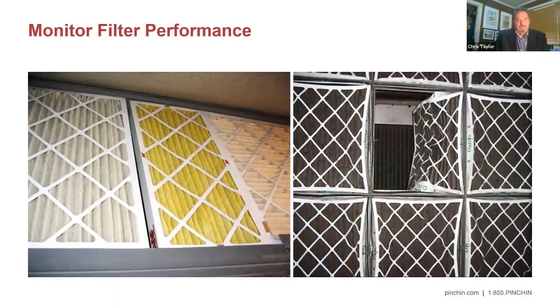Here's where maintenance comes in. When we're doing inspections, probably the number one thing we see is either damage to filter banks with clear penetrations, or where people have ill-fitting or misfitting filters they've grabbed and stuck in there. In both these pictures, we may have very good filters that aren't doing anything, because with the openings available, air finds the easiest path through, and you're just not going to get the filtration you need. So make sure you inspect all of your systems.